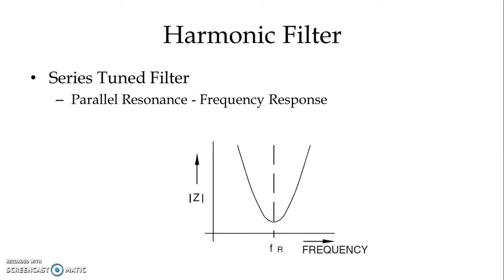Looking at the frequency response, we have impedance plotted against resonance frequency. At a certain frequency the impedance is lowest. To avoid parallel resonance, we normally do not design our filter at exactly the harmonic frequency to be filtered. For example, if we want to filter out the fifth harmonic, we design our series tuned filter for the 4.7th harmonic. This minimizes the possibility of parallel resonance between the filter impedance and the source impedance.